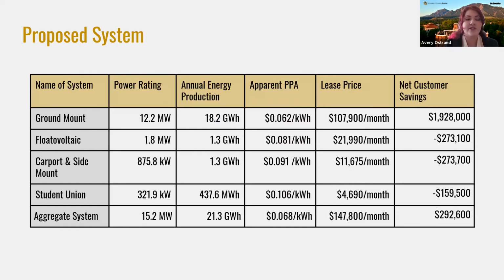After we finished the iterative financial process to find the most beneficial system economics, we decided on this combination for our recommended system. In total, it's about a 15 megawatt system with the addition of a 361 kilowatt battery and a monthly lease price of around $148,000. Knowing UCF's want for carbon neutrality and more sustainable energy independence, we sized the system to be as large as possible while remaining under the net export constraints set by Duke Energy, since UCF cannot sell back or export more energy than the equivalent of its daytime load.